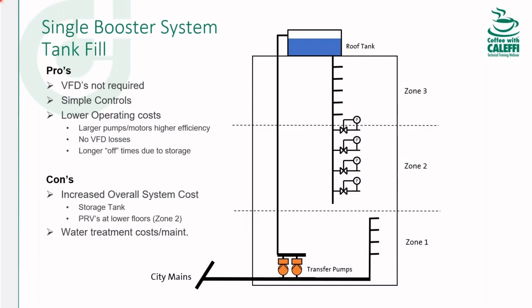The other side of it is that the system cost can be much more expensive because you have to have this large storage tank on the roof that takes structural cost, the cost of the tank itself. And then you still do need the PRVs at the bottom, but you're going to need PRVs anyways in a very high rise building. And now you have this large mass of water, so you might bring in water treatment concerns because you have a lot of stagnant water there. So how does that play into the quality of the water, the cleanliness of the water, bacteria growth, and things like that? That's another consideration with a large storage of water like this.